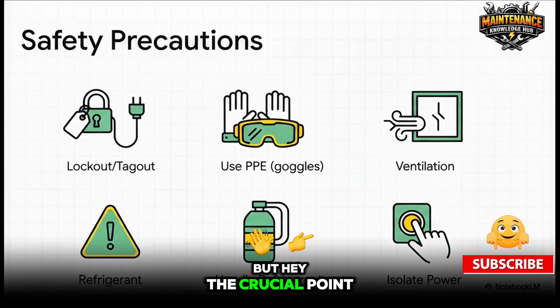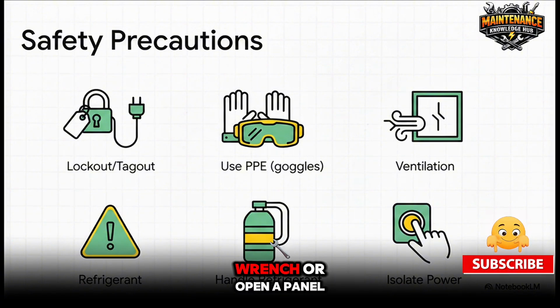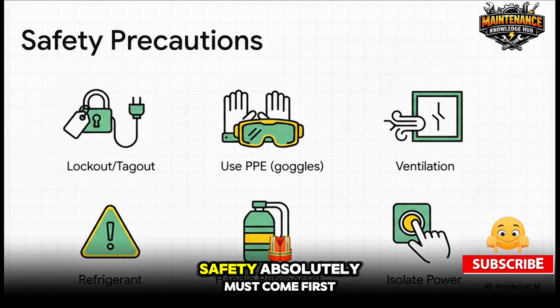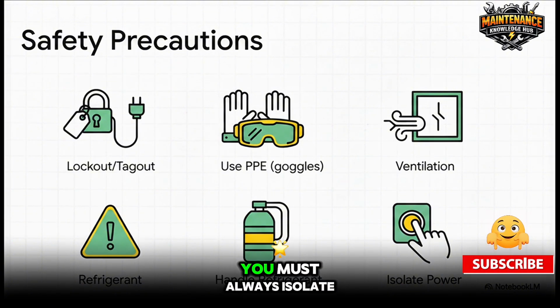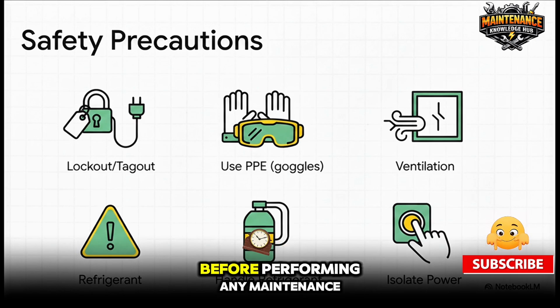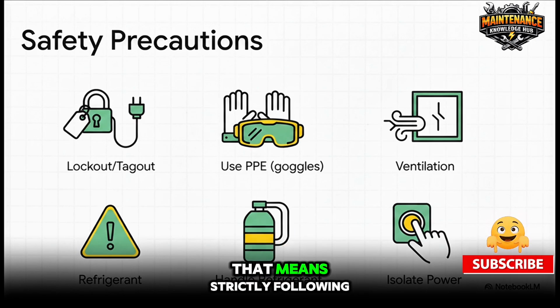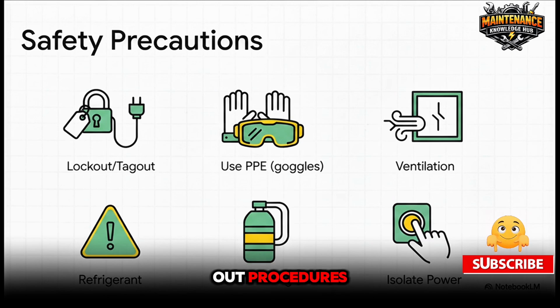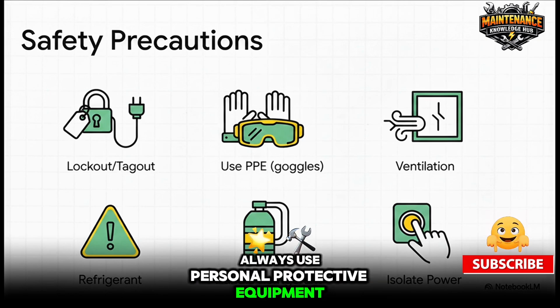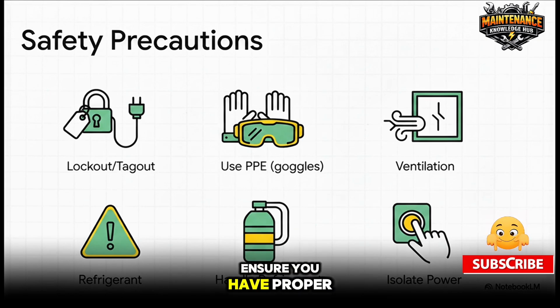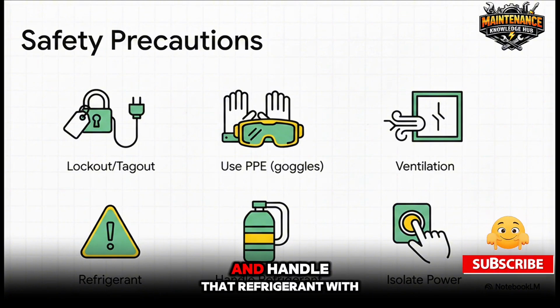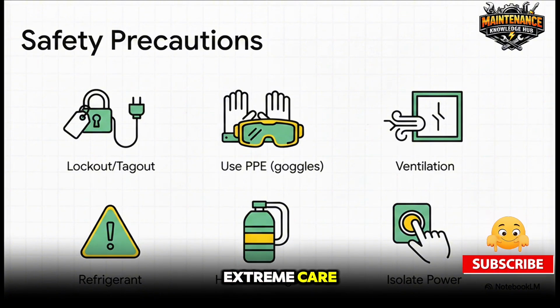But hey, the crucial point here is before you grab a wrench or open a panel, safety absolutely must come first. You must always isolate the power before performing any maintenance. That means strictly following lockout and tagout procedures so no one accidentally turns the machine on while you are actively working on it. Always use personal protective equipment like gloves and goggles, ensure you have proper ventilation in your workspace, and handle that refrigerant with extreme care.